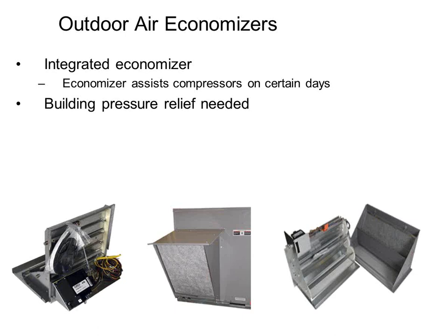out. On small rooftop systems, we typically use a barometric relief damper, which is nothing more than a piece of sheet metal with a little counterweight action to it, and I have to build up the pressure in the building to push the sheet metal open and relieve the air.